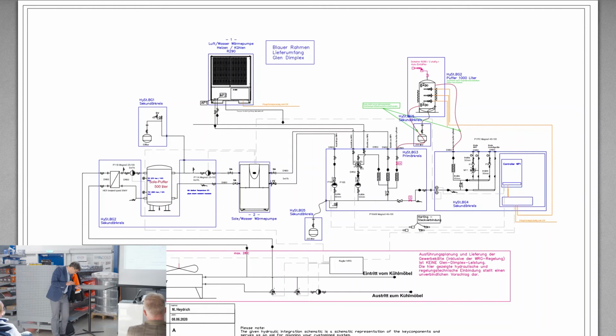Then the energy is taken and collected in the secondary buffer, and this is the source of energy for the rest of the installation. Then we have circuits for the installation: the circulation pump, and some mixing valve is necessary if we need to reduce the temperature, for example for an underfloor heating system. There is other equipment here.